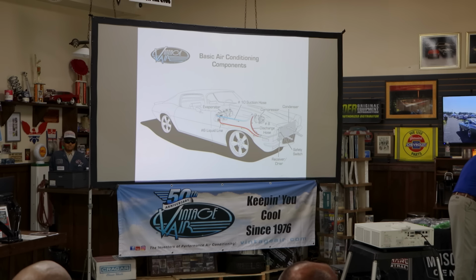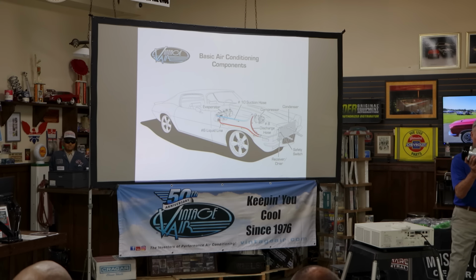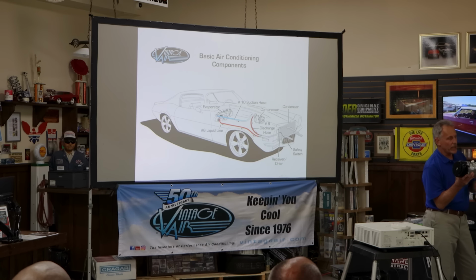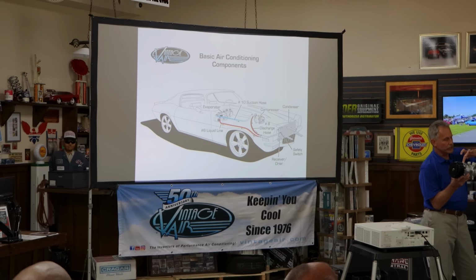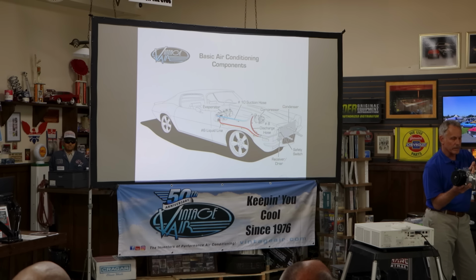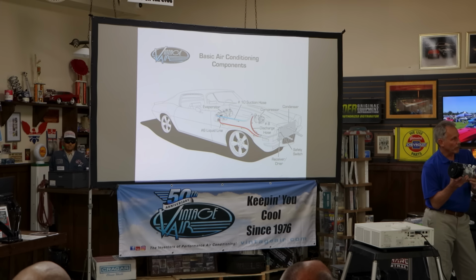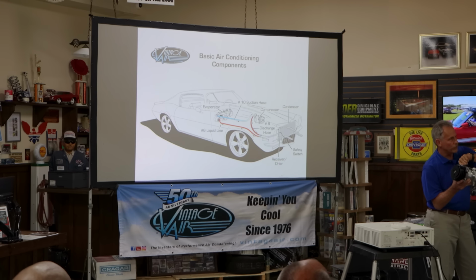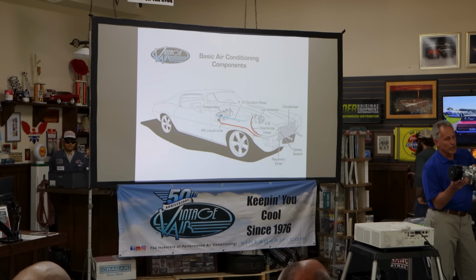These compressors people call a rotary, but this is actually an axial compressor. What you've got, you don't have a crankshaft in this, you've got a wobble plate here. The pistons, you can see the cylinders on the body of this, move back and forth this way. So here's the head, your suction and discharge.